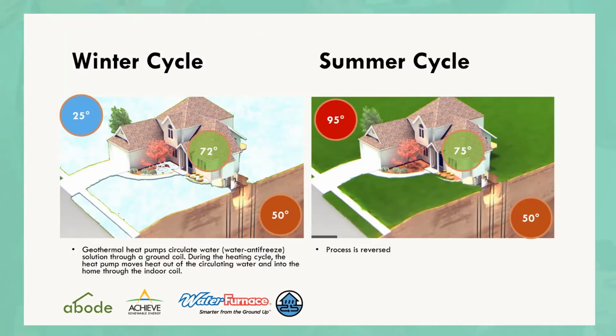In the wintertime, when it's cold outside, the ground source heat pump doesn't have any consideration for what the outside temperature is because it's not exchanging with that outside environment. It's exchanging with the ground, which in our area starts somewhere between 50 and 55 degrees at the beginning of the season. Depending on the ground source option that's selected, that temperature might fluctuate over a heating or a cooling season. But at any rate, the exchange is with a temperature that's much more moderate than the outside air. So that's why the ground source heat pump efficiencies are a multiple of the air source heat pump efficiencies.